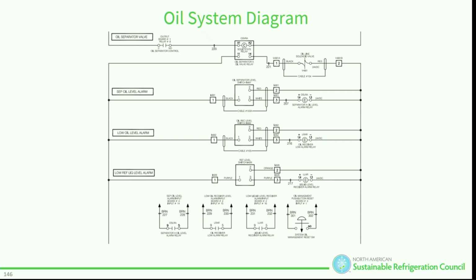All right, so again, we have our OS, and let's go over the refrigeration switch. The oil reservoir switch works exactly the same way, but they've only got the 2 relays and 1 input. They don't have the rest of it, the flex combiner that cycles your pulse count card, your solid state card, and your solenoid. So we're going to have fluid present. The switch is going to go from flashing green to flashing red. That's going to energize leg number 3, which energizes our OSLAR relay, oil separator level relay alarm. That's going to make a closure to our input board through our cube relay. Our cube relay will turn on green, it's 24 volt DC.